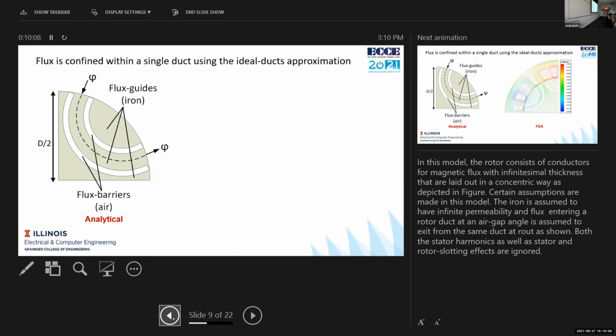There we go. Let's look at what happens when we include the stator winding harmonics. Right now what I'm showing you is, again, a simplified version of a BDFRM, and I've excited only my primary stator. If we look at the magnetic potential of the stator, or the MMF function, we can see that after including the winding harmonics, our estimation of magnetic potential improves as compared to without winding harmonics. So that's how we can, first of all, increase the accuracy of the stator winding harmonics.